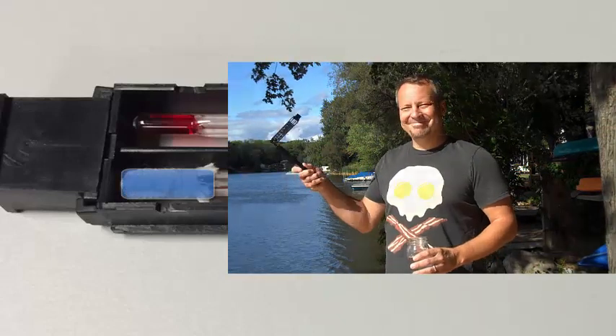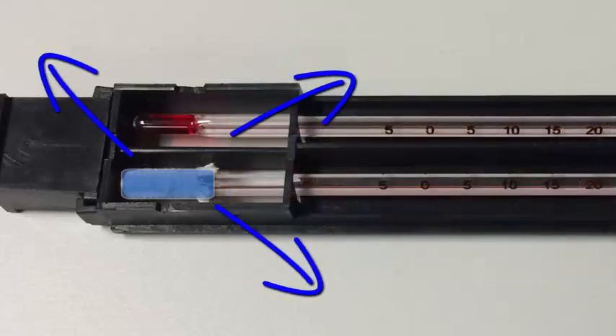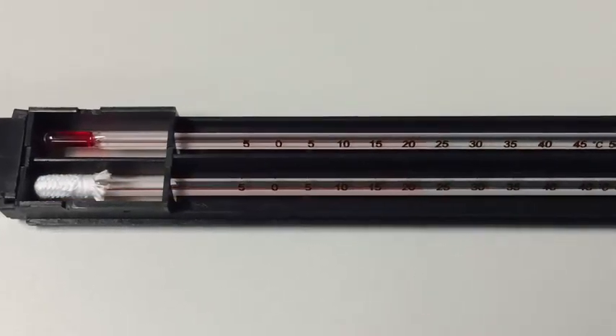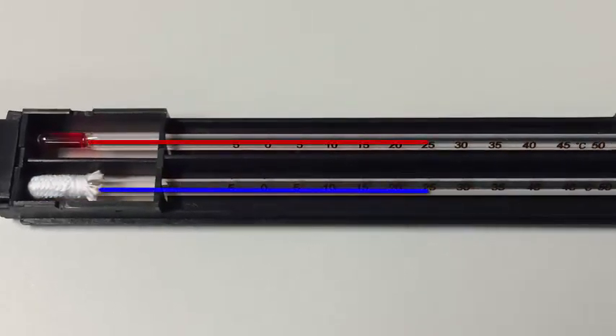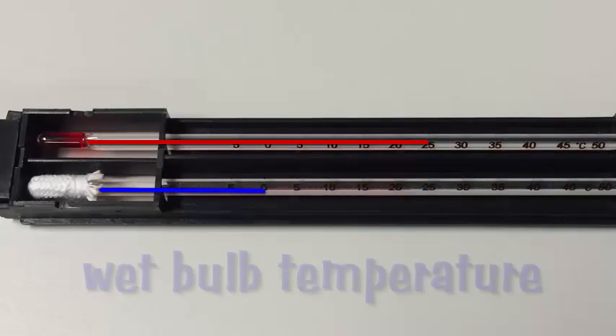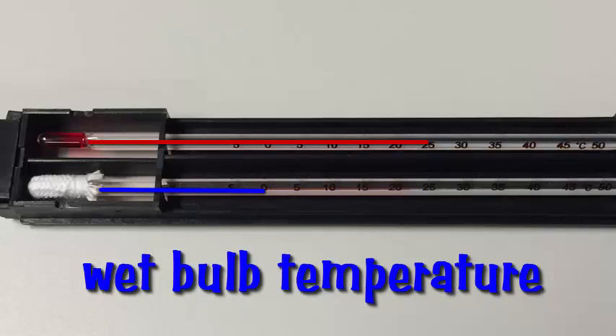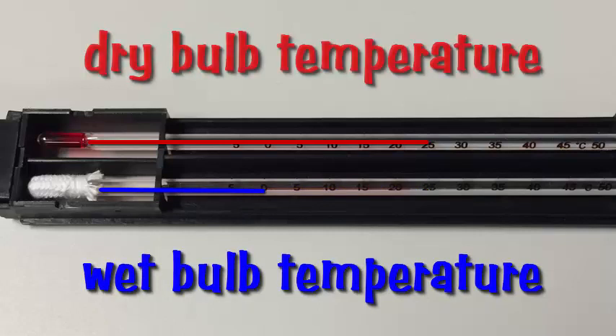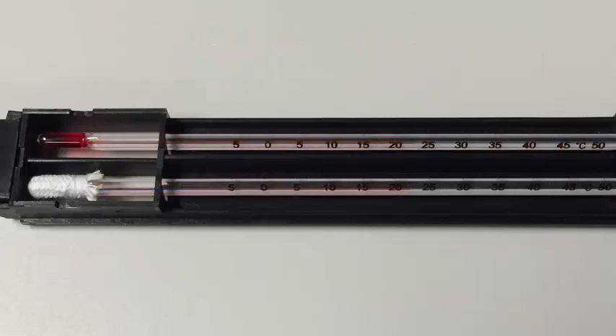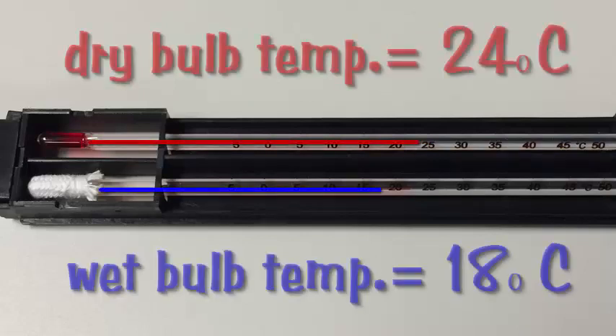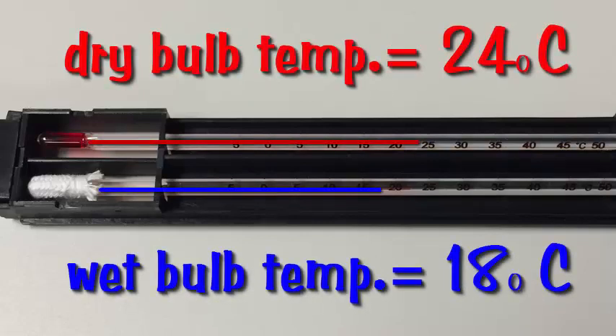As we're spinning it, water evaporates from that cloth. And as you know now, evaporation is a cooling process. So we should see that the temperature on that thermometer goes down a bit. We call that temperature the wet bulb temperature. The other thermometer is dry, so therefore we call it the dry bulb temperature, and that really just measures the air temperature. So let's say you measured a dry bulb temperature of 24 degrees Celsius and a wet bulb temperature of 18 degrees Celsius. Here's how you would find the relative humidity and dew point temperature.